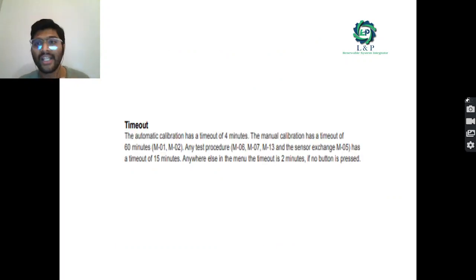And most importantly, if your device is not being used for more than 4 minutes, the timeout will happen automatically. You can also change the timeout settings. For manual calibration, the timeout is 60 minutes, that is for menu 1 and 2. For any test procedures, that is M6, M7, M13, and the sensor exchange process, the timeout will be 15 minutes. Anywhere else, the menu timeout is 2 minutes if no button is pressed.